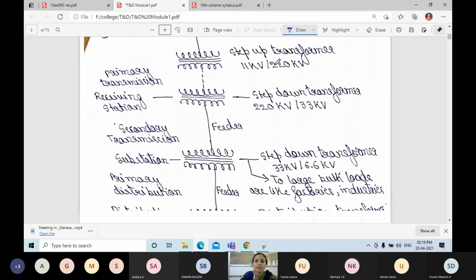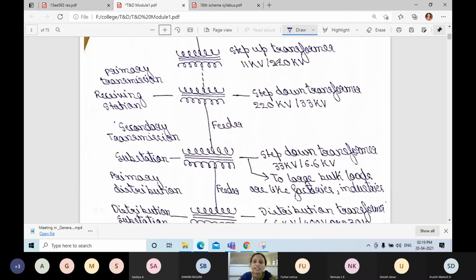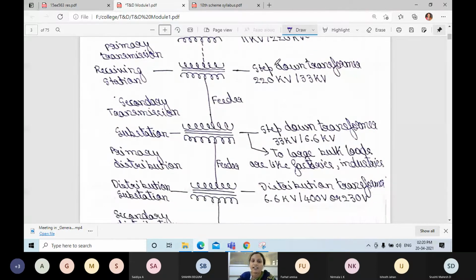And next, here the feeder. Okay, between the receiving station and the substation, there is a line called the feeder. Okay, secondary transmission. This is the primary transmission from 11 kV to 220 kV. And next, secondary transmission. Secondary transmission, step down transformer.